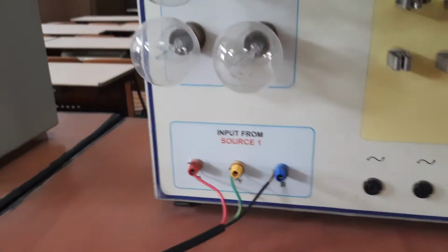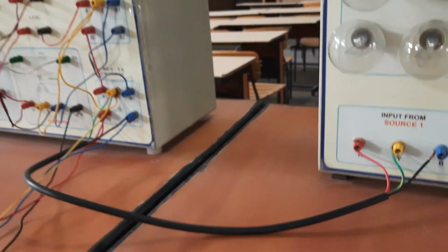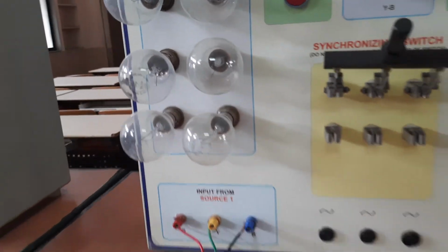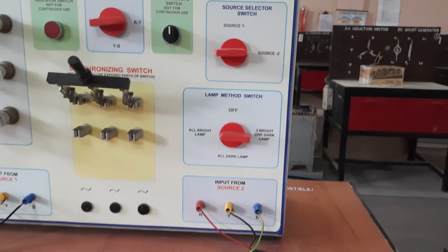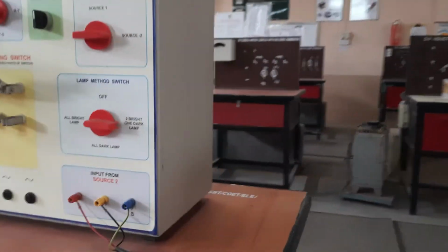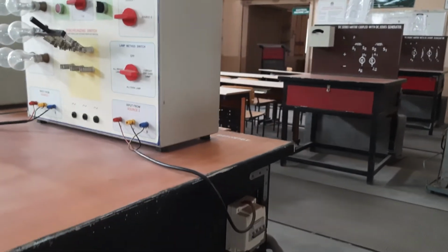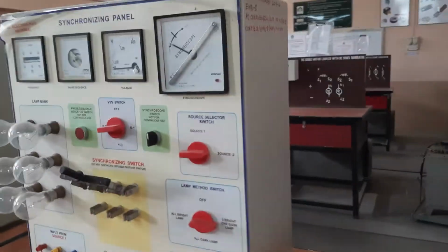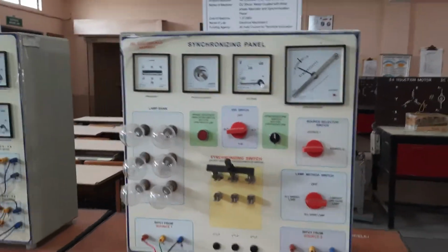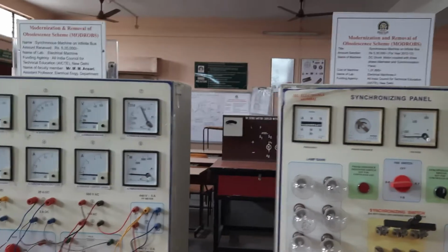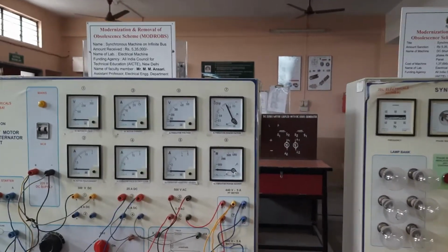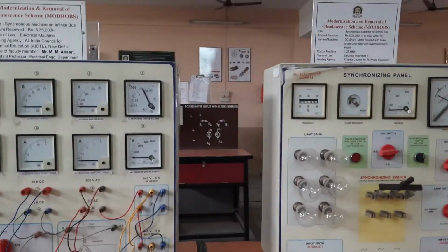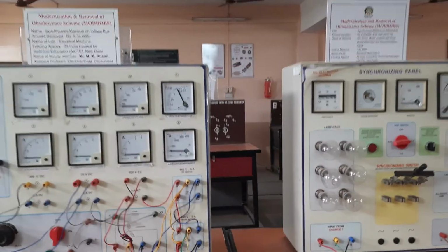See here, this is the wire connected with the panel. So it is the source connected from the alternator, whereas the second source is connected to the grid. Now this is the grid switch. After switching on the supply, we can compare the voltage and frequency. Once the voltage and frequency of the incoming machine are equal to the grid voltage, it is ready to synchronize.